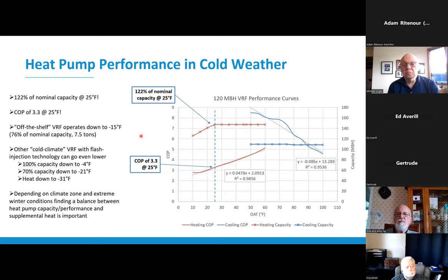But let's say you're in an even colder climate. What do you do then? So there are VRF systems with something called a flash injection technology that can go to even lower temperatures. So these types of systems can deliver 100% capacity down to negative 4 degrees, 70% capacity down to negative 21 degrees, and still deliver heat down to negative 31 degrees.